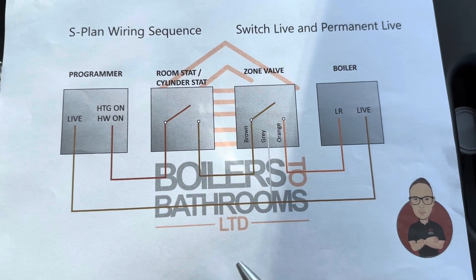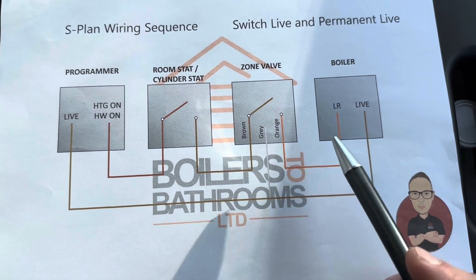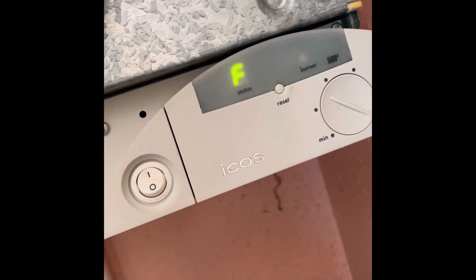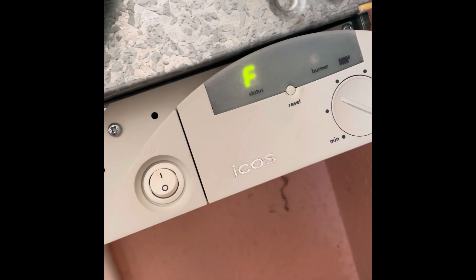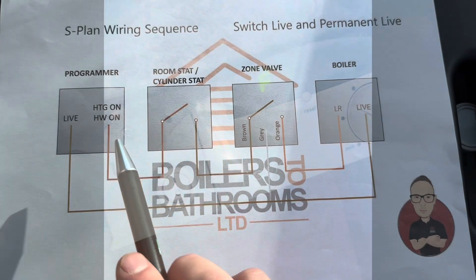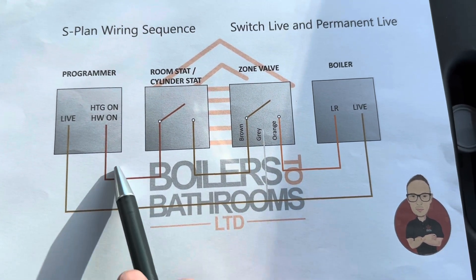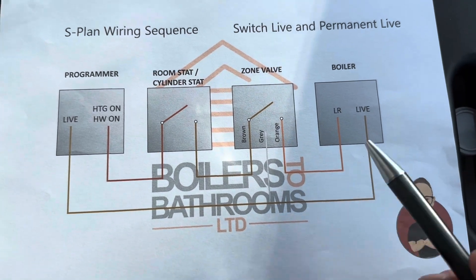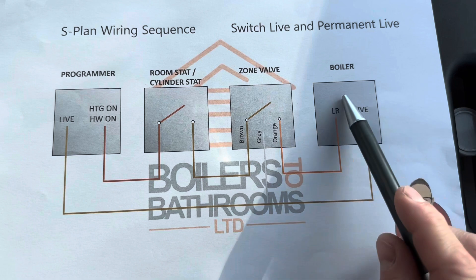Another no-heating fault: you get to the boiler and it's flashing, coming up with a fault code. In that case we know the wiring path is okay because we're getting 240V on the live return to fire the boiler in the first place. The boiler itself has a fault on it, so that's where we're looking for the problem.